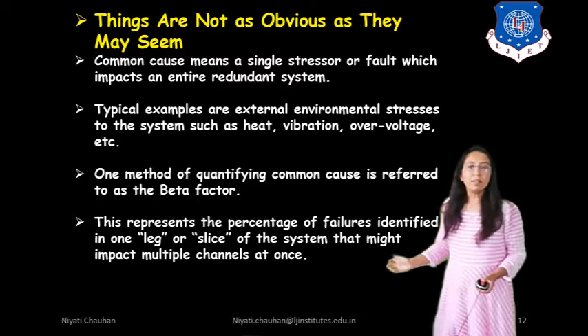Common cause means a single stressor or fault which impacts the entire redundant system. Typical examples are external environmental stresses to the system such as heat, vibration, overvoltage, etc. One method of quantifying common cause is referred to as the beta factor. This represents the percentage of failures identified in one leg or slice of the system that might impact multiple channels at once. Various standards groups worked for years trying to resolve this issue.